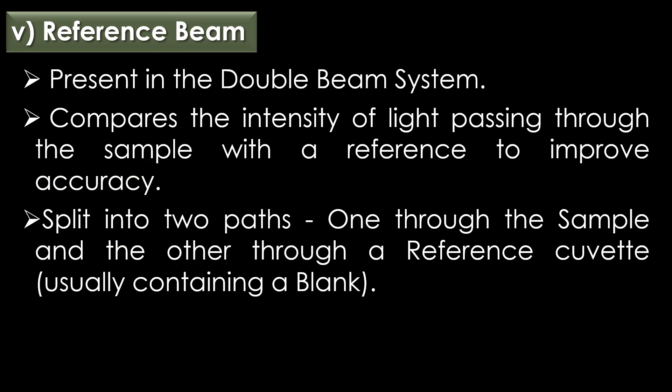Reference beam: the reference beam is present in the double beam system. It compares the intensity of light passing through the sample with a reference to improve accuracy. The beam is split into two parts — one through the sample and the other through a reference cuvette, usually containing a blank.